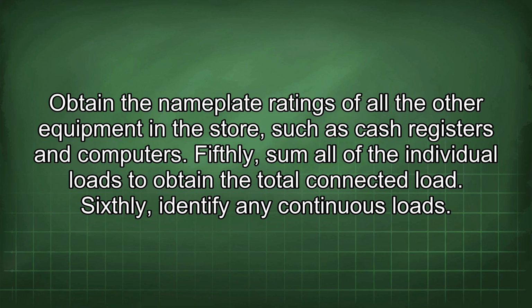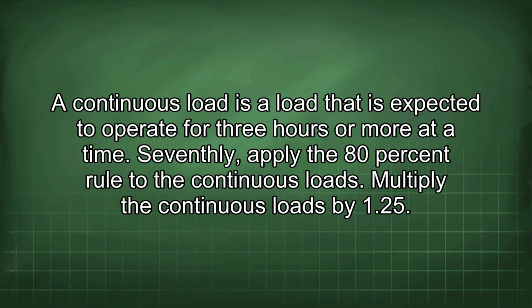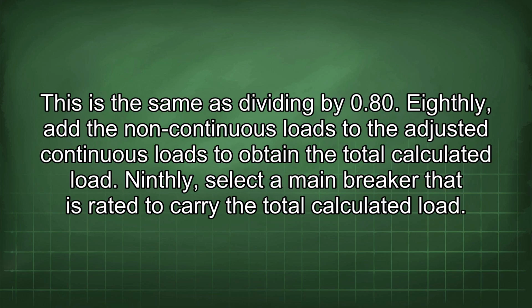Sixthly, identify any continuous loads. A continuous load is a load that is expected to operate for 3 hours or more at a time. Seventhly, apply the 80% rule to the continuous loads. Multiply the continuous loads by 1.25. This is the same as dividing by 0.80. Eighthly, add the non-continuous loads to the adjusted continuous loads to obtain the total calculated load.